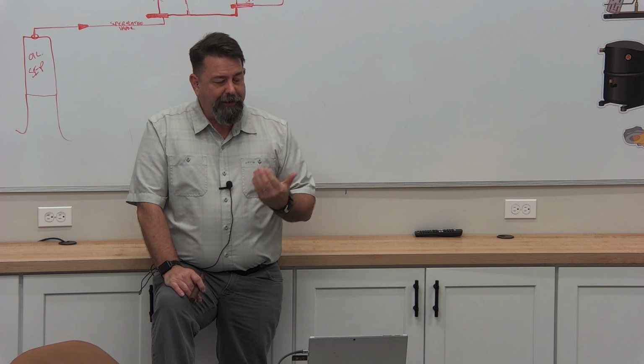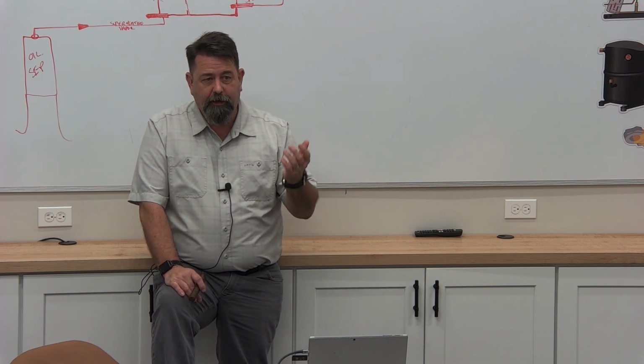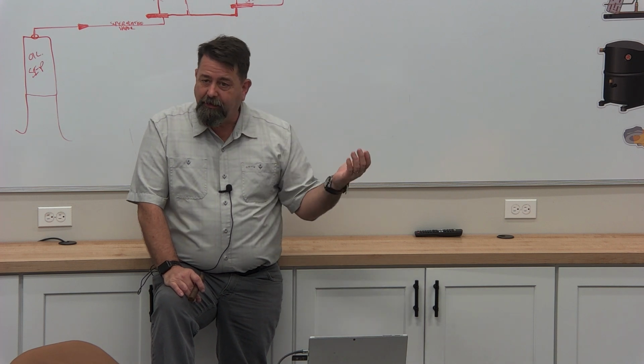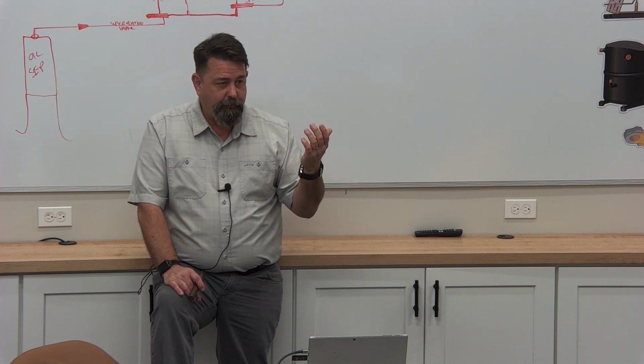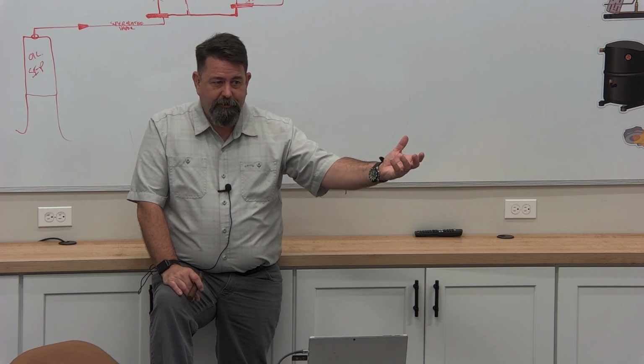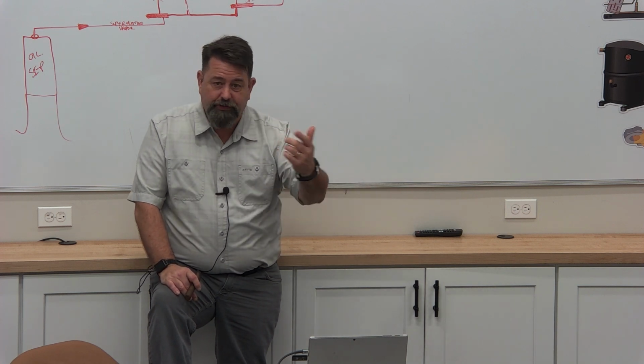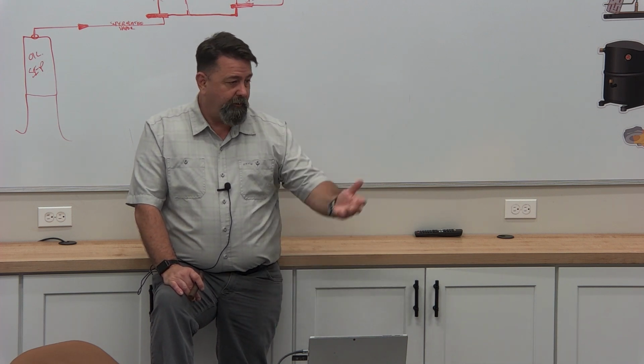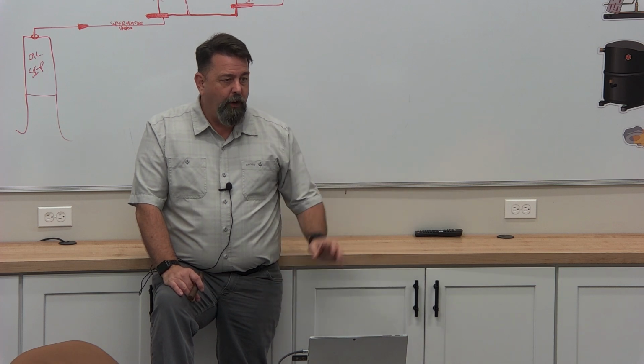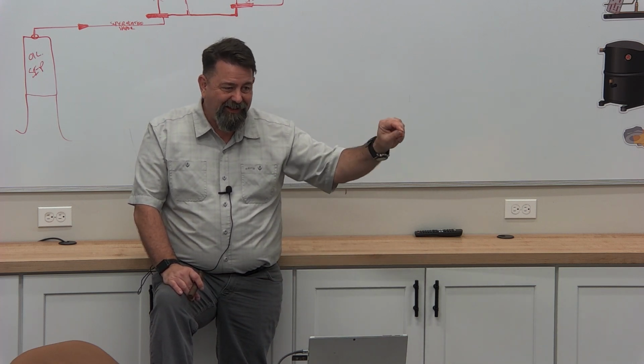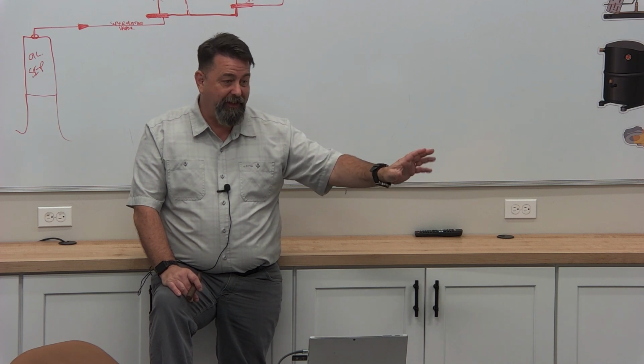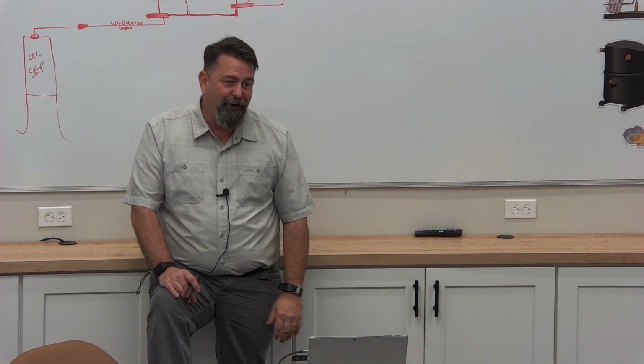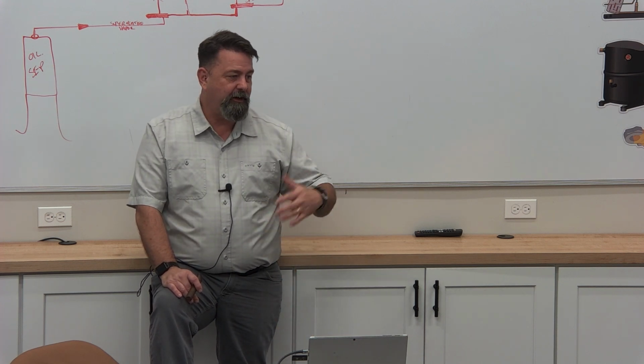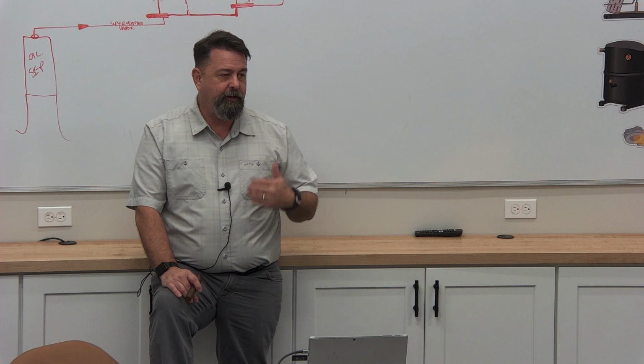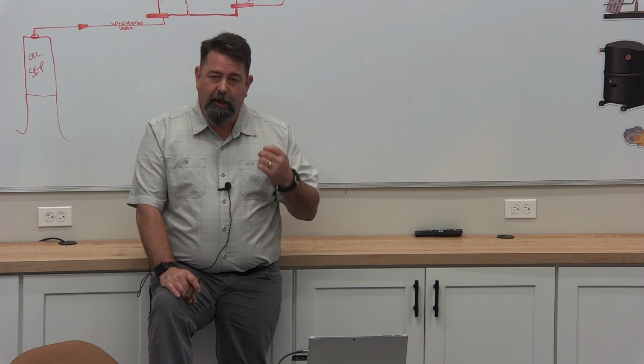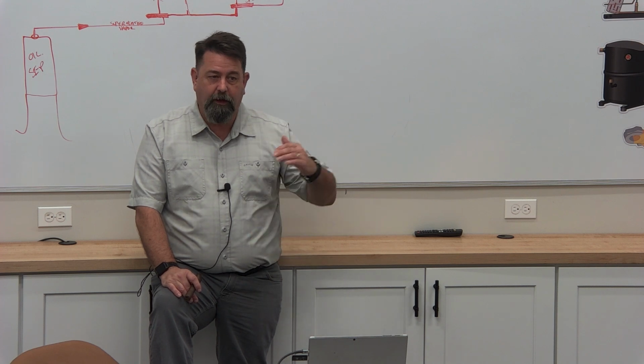Now, the other downside to controlling that way is I may have 6 cases on that circuit. When I say I'm controlling off of that circuit, what am I controlling off of? The sensor. I'm either controlling off the average of all 6 or 1, right? In the case of Novar, it's just 1. So I'm running the entire rack off of 1 case. Well, that's dumb. We can think of lots of things that could go wrong with that, right? I lose a fan motor, whatever, the entire rack changes, right? So anyways, that's the disadvantages of it. The advantages are what Corey just said. Power, man, they save a lot of power by letting that suction drift up.